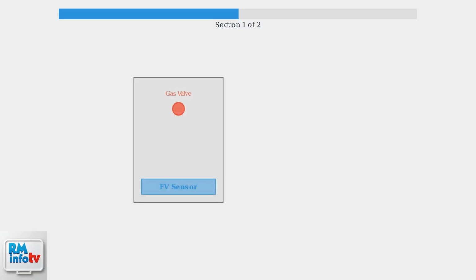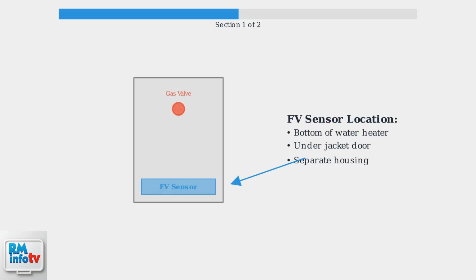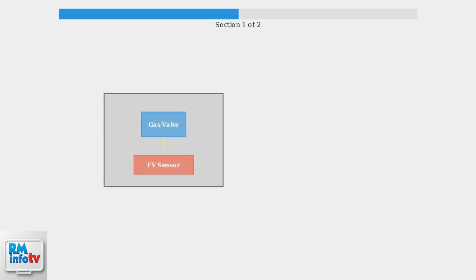The FV sensor is typically located near the bottom of the water heater, often beneath the jacket door or in a separate housing. This cutaway view shows the internal components and where the sensor monitors for flammable vapors. Here you can see the actual FV sensor on a Richmond water heater. The sensor has a clear warning label that reads Flammable Vapor Sensor, Do Not Block. This sensor communicates with the gas valve through a wire harness.